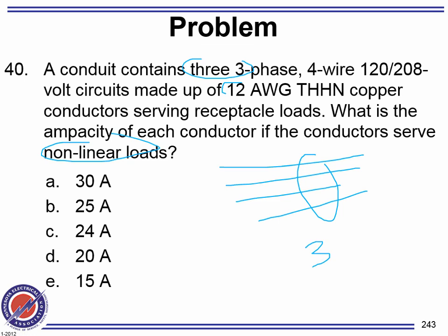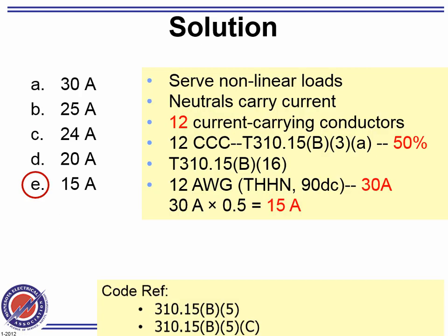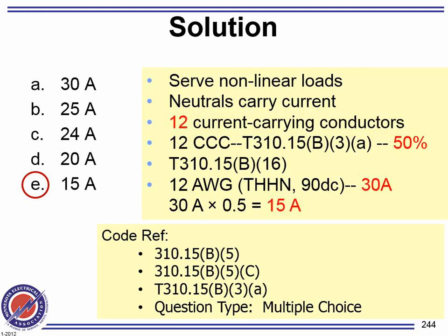12. Does the neutral count? Yes. If they say the neutral is carrying a nonlinear load, which is a harmonic-rich load, then you count it as a hot. So these are 3 hots, and then they will count as what? 12. So here you go. So 12 of them. For 12 conductors, gentlemen.